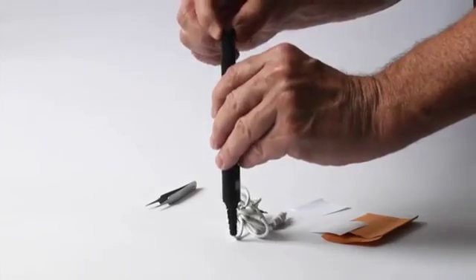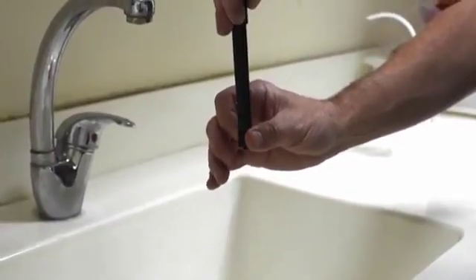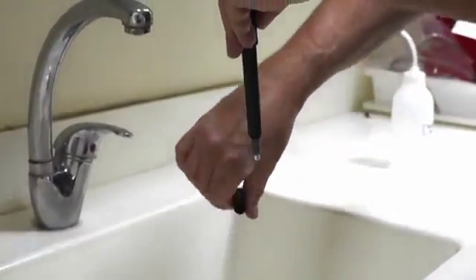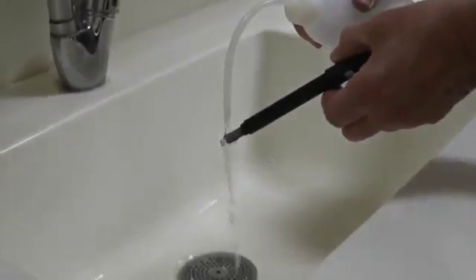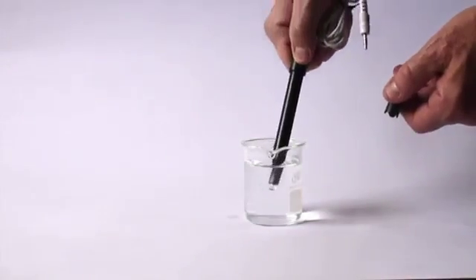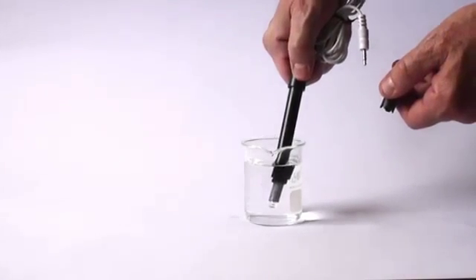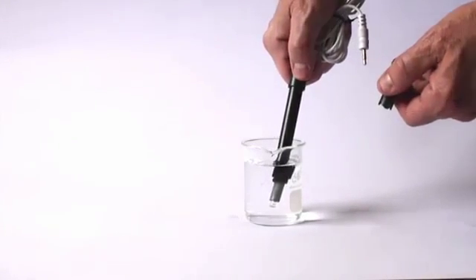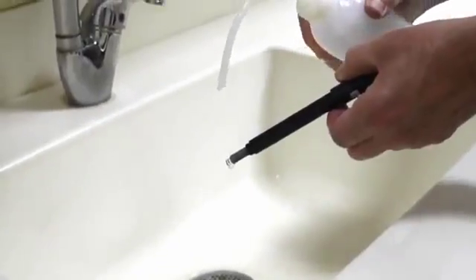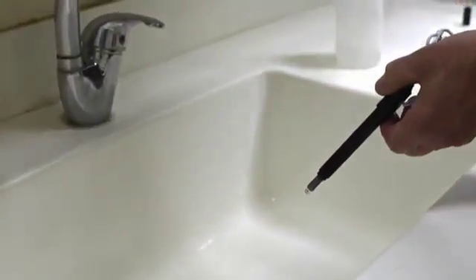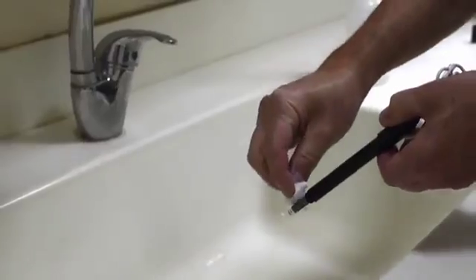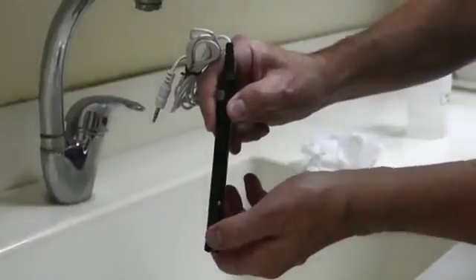The dissolved oxygen sensor also needs to be cleaned periodically. To clean the sensor, unscrew the cap, rinse with distilled water. Soak the tip of the probe in a hydrogen chloride solution for 15 to 20 minutes. Consult the datasheet available on einsteinworld.com for details about this solution. Rinse the tip with distilled water and blot dry. Replace the membrane. Refill the cap with fill solution and screw back on.